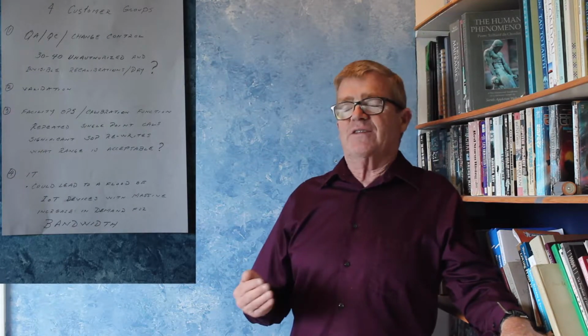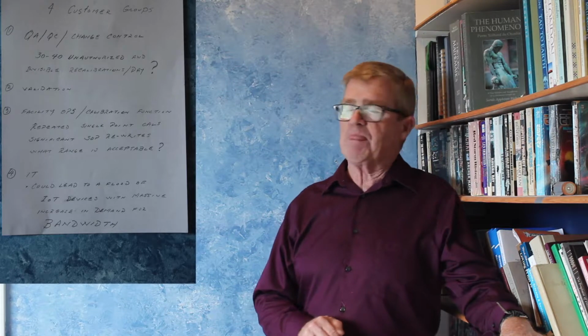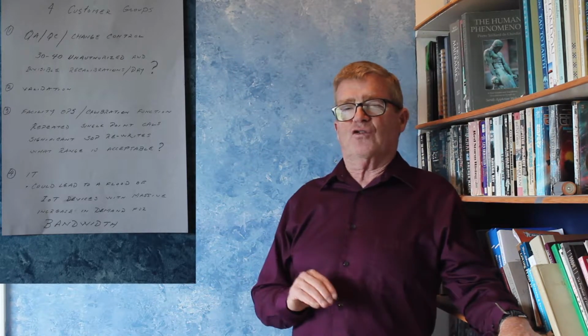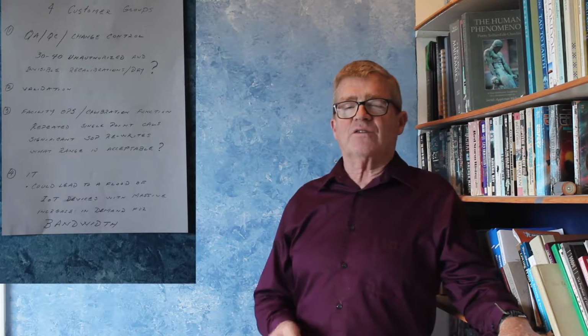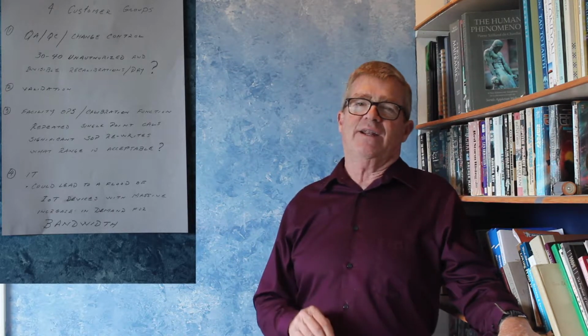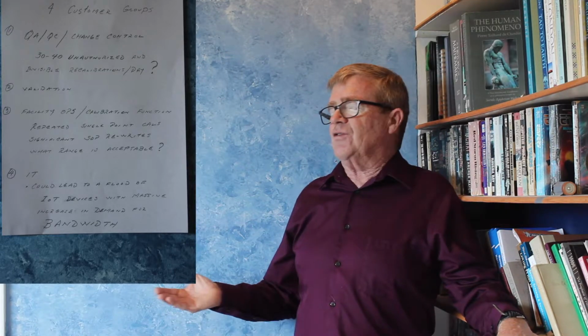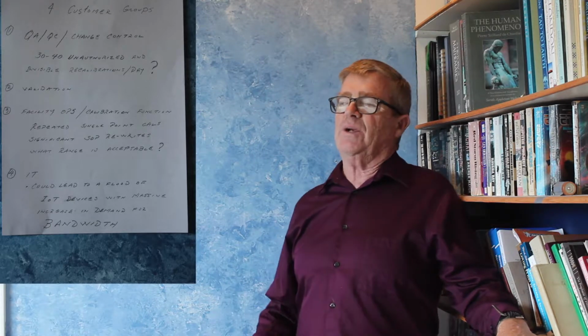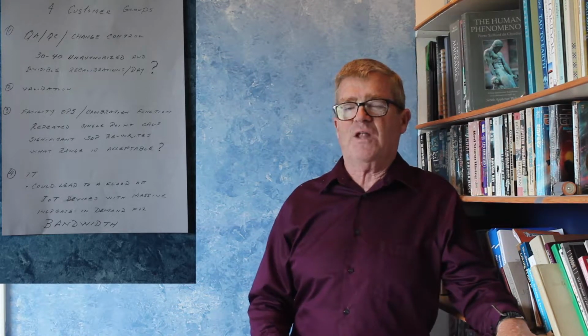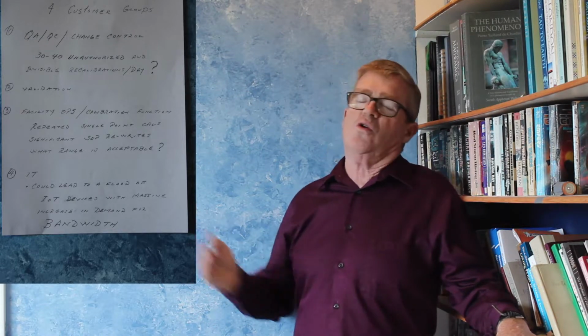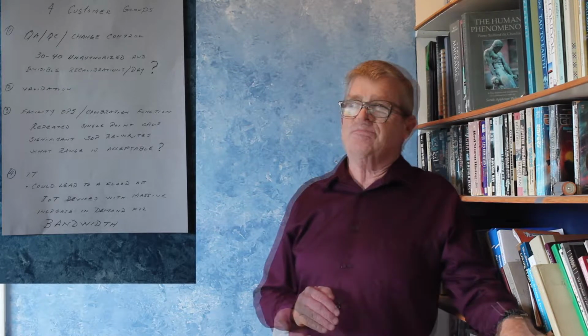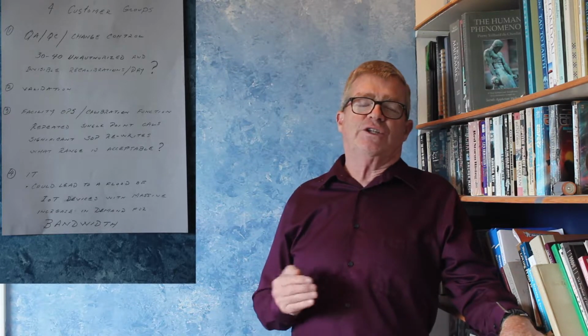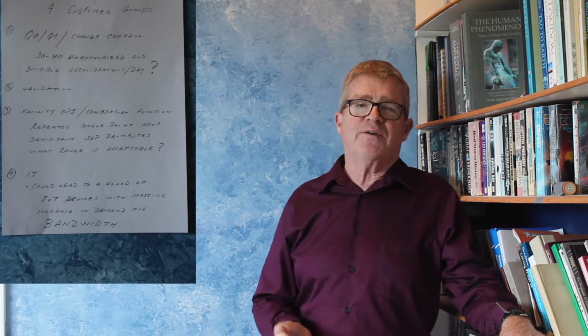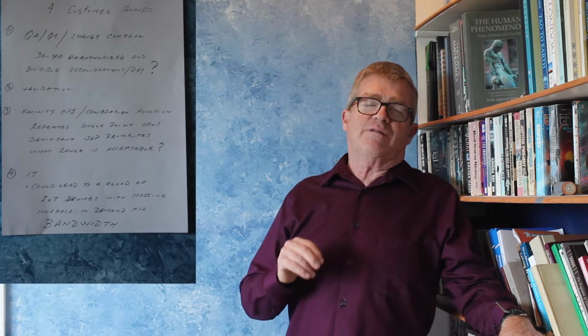Were we to buy this device in Pharma, I can think of 4 different groups of people that would want to be at the table. First group is quite obvious. It's the change control guys in QC or QA. From their point of view, we might look at all the switching that's going on as unauthorized and unscheduled activities against a validated instrument. They might say it's unauthorized because there's no signature from a supervisor saying, yeah, calibration tech, go out and calibrate that device. It happens on the fly. They might say it's unscheduled because there's no work order associated with this activity. So are these reasons enough for a change control guy to choke on this proposal? I don't know. Next group at the table is the validation crew.